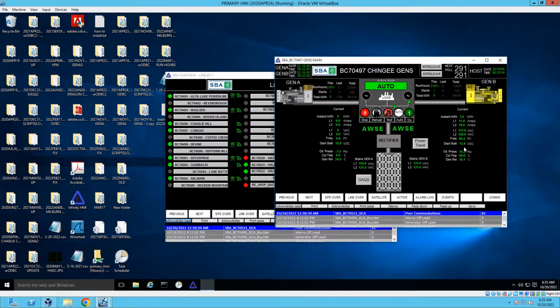The starting battery voltage, oil pressure, cylinder temperature, and generator room temperature are also included, to assist in detecting any issues. This metering is completed for both generators, and semi-annually the generators are switched so that generator A would run prime, and generator B would function in a standby capacity. We also have for each generator indicators for alarms, warnings, shutdowns, and emergency conditions that will turn red in the event they are tripped.